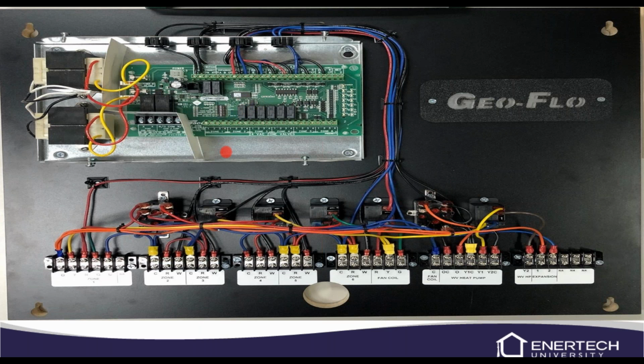And so we would need to be able to do cooling as well with this panel. So we've had to add relays so we can shut off radiant zones when we're doing chilled water. We don't want chilled water going through our radiant zone. So in the future, once we get our connected controls, we can get rid of some of these relays. But for now, we've already got them factory wired for you. And this is a real plug and play.